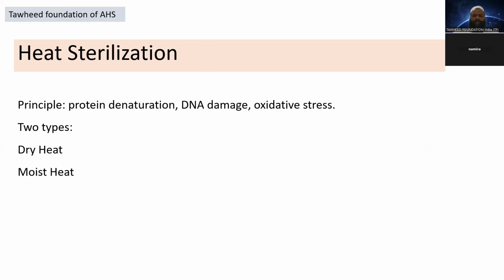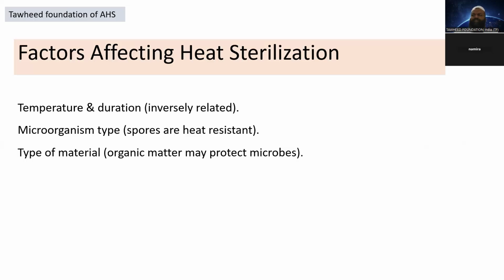There are several factors that can influence the heat killing procedure, such as factors affecting heat sterilization. Temperature and duration, inversely related. Microorganism type, spores are heat resistant. Type of material, organic matter may protect microbes. So we'll start with temperature and duration. The duration and temperature are inversely connected to each other. Therefore, in the case of a long duration of heat provided for sterilization, the temperature will be reduced, while in case of high temperature, the duration will be reduced.